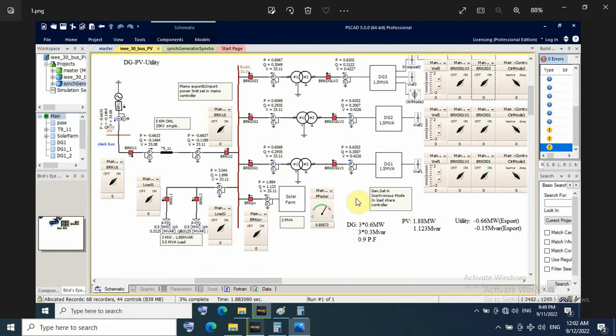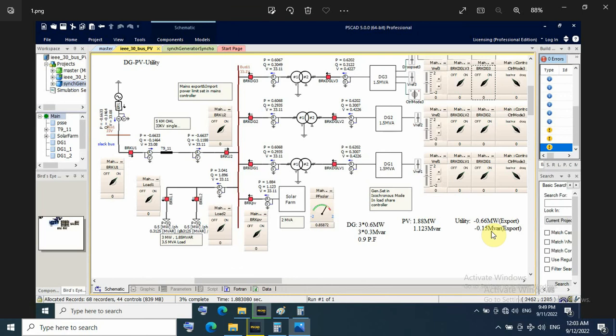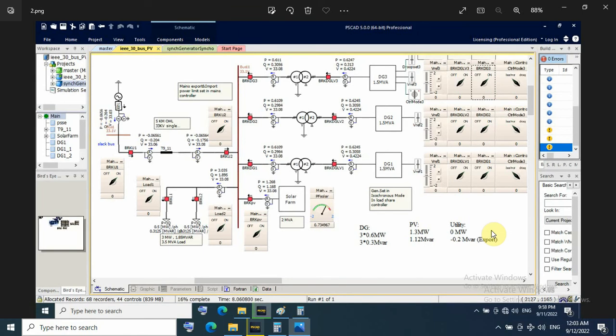So here in normal operation, DG generate for each genset about 0.6 megawatt and 0.3 megavar at power factor 0.9. PV generates 1.8 megawatt and 1.1 megavar. Utility side, here in this case not import power from utility, but export power to utility, about minus 0.6 megawatt and minus 0.15 megavar as export.